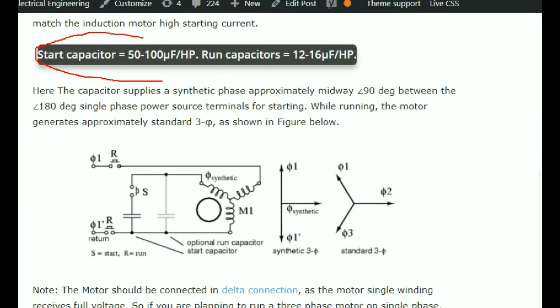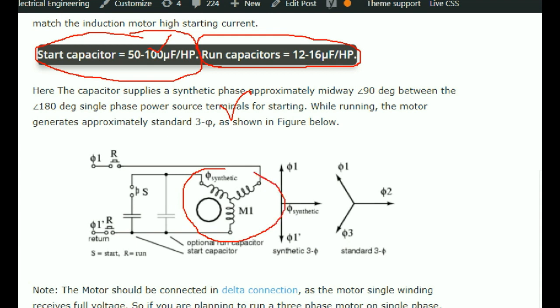The start capacitor value is 50 to 100μF per HP. So one HP can go up to 100μF, and the running capacitor can go to 12 to 16μF. What is recommended is delta configuration — there is a voltage distribution for the windings. If you have a star winding, you share two voltages; if you have a delta winding, you share one winding with one voltage.